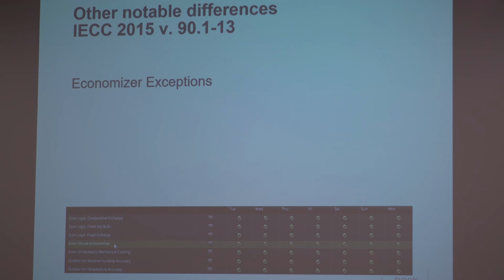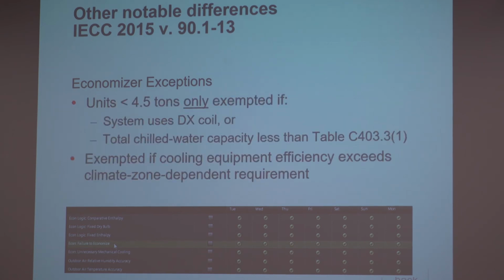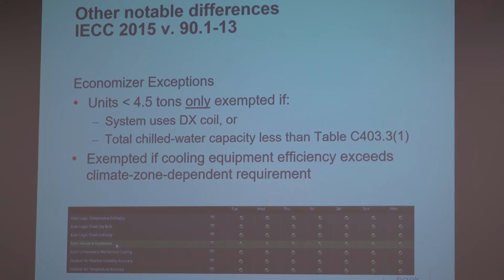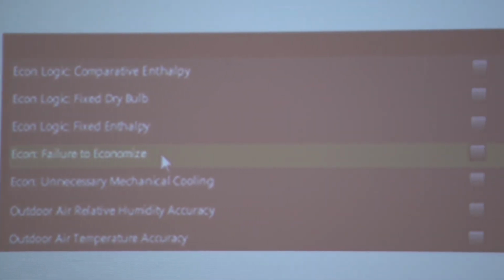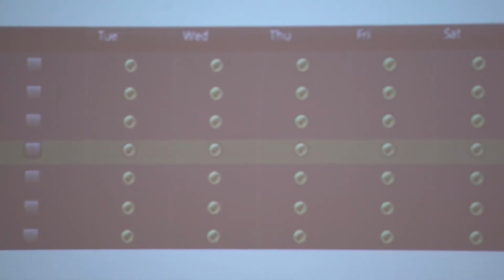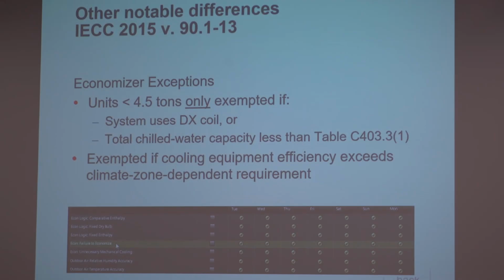Okay, fault detection. Fault detection's image is at the bottom, but we're still talking about the economizer exceptions. So in IECC, this aggregation clause still exempts the DX coils. So if you have a direct expansion coil, such as one in a packaged terminal air conditioner, or maybe in a water source heat pump, or a VRF system, then this aggregation clause doesn't apply to you. And that's, to be honest, one of the reasons why 90.1 didn't like the way it was written, because it seemed to pick winners and losers. And we wanted to find a more comprehensive way to incorporate all terminal products, not just some of the terminal products. Some progress has been made towards that end, but we haven't finished that process yet.